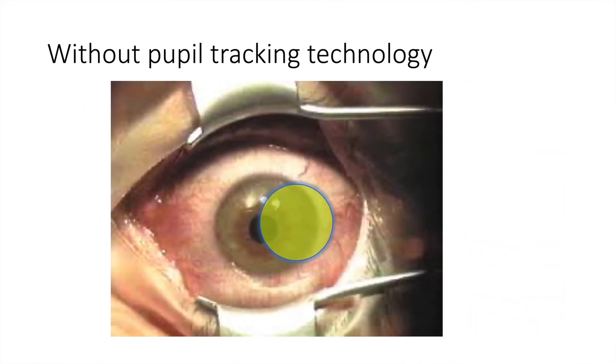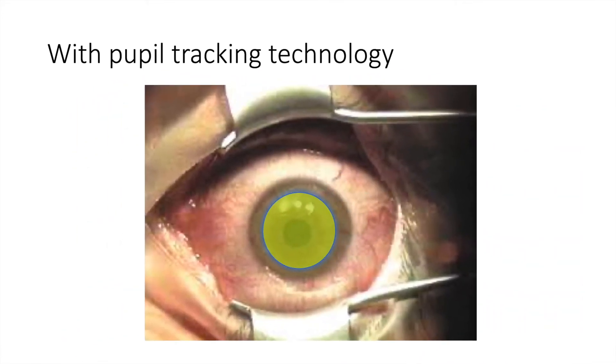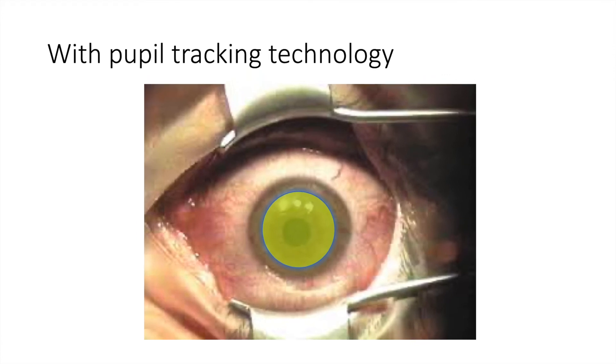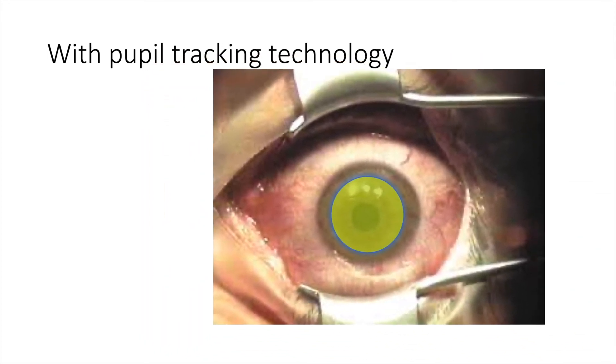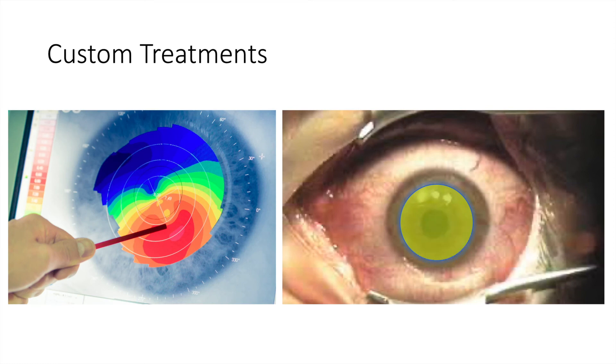The Avedro KXL2 machine tracks a patient's pupil in real time, so as a patient's eye moves, the machine moves the ultraviolet light with it. This has the advantage that all of the ultraviolet light is delivered exactly to the part of the cornea where it's needed. But more importantly, the dosing of the ultraviolet light can be altered so that the steeper parts of the cornea receive a higher dose of ultraviolet radiation, meaning the patient's cornea can be improved, not just strengthened with the procedure.